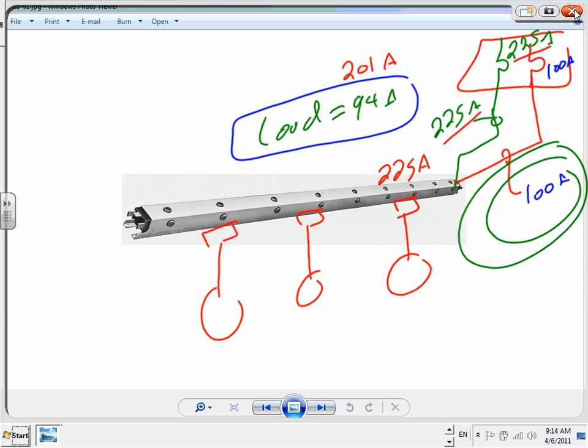I really don't know. I can throw a 10-foot section and say maybe $5,000. If I were to guess, I would say $5,000 for a trolley busway with the hardware that comes with it, 2 devices and so forth. They're definitely more expensive than plug-in because now you have moving objects, and you have moving objects while energized.